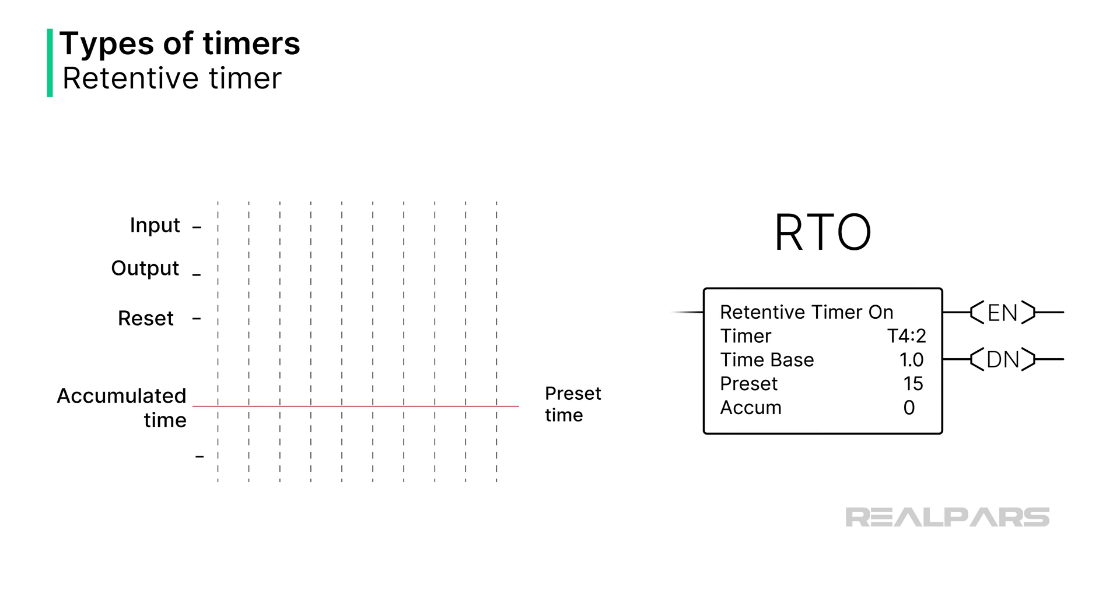This type of timer is like the on-delay timer, except the timer does not reset when the timer input goes false. The accumulated time is preserved, and when the timer is enabled again, it continues to accumulate time until the preset time is reached. At that point, the done bit is set. With a retentive timer, a reset instruction must be executed to reset the timer.